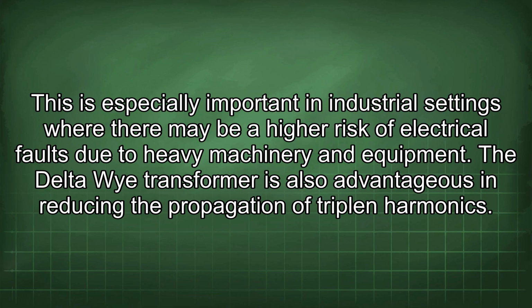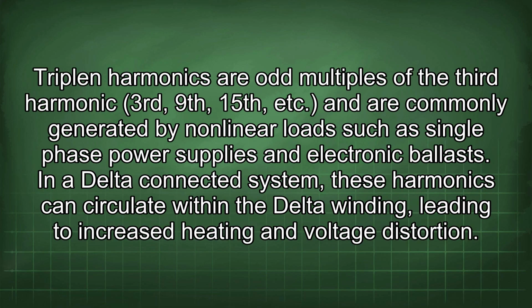heavy machinery and equipment. The Delta Wye transformer is also advantageous in reducing the propagation of triplen harmonics. Tripling harmonics are odd multiples of the third harmonic (third, ninth, 15th, etc.) and are commonly generated by nonlinear loads such as single-phase power supplies and electronic ballasts.